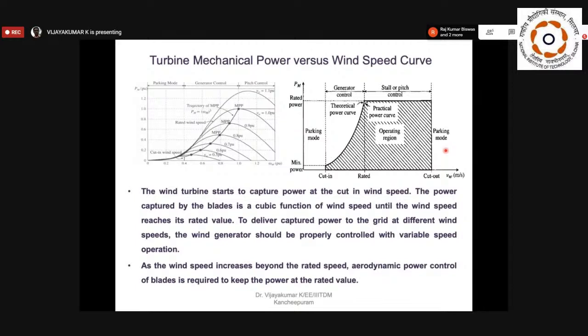The reason is, if you allow the turbine to rotate above cutout speed, it leads to damage to the turbine systems because of the gusty wind speed. At that time, by changing the tilt angle of the blades as well as through electrical control, you can stop the wind turbine from rotating during gusty wind speed. Right, so this is the characteristics of the wind turbine.